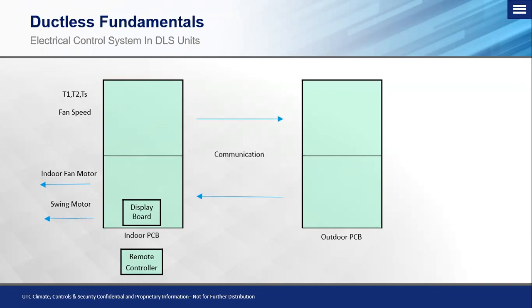Now we look at the communication between the indoor and the outdoor boards, because they have to talk for this system to work properly. Communication is carried between the L2 and the S wires on a 208, 230 volt system. On a 115 volt system, that communication is carried between neutral and the signal wire. Okay. And that's how they talk between indoor and outdoor. Now, I could go in and start to tell you the troubleshooting processes, but I really think that's diving a little bit too deep for this particular class. So for right now, we're just going to understand where it's carried between. And in later classes, we'll cover how to troubleshoot what's good and what's bad.